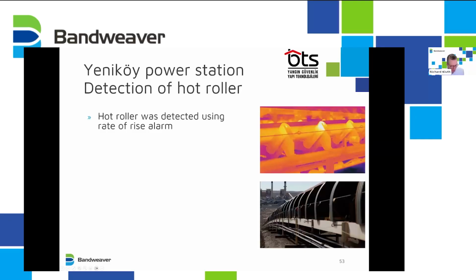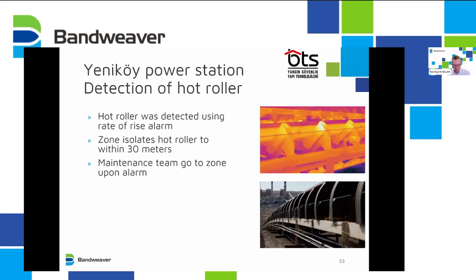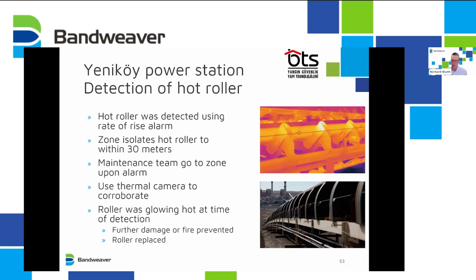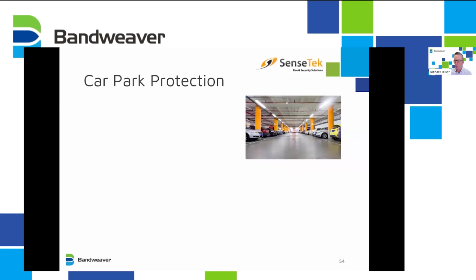And again, a successful fire prevention detection here. Hot roller was detected using the rate of rise alarm. The zone was isolated within 30 meters. The maintenance team went to the zone upon alarm, used the thermal camera to corroborate. It was glowing hot, so no further damage or fire. Roller replaced. Again, this could have been a massive incident, but was stopped before the fire was allowed to develop.